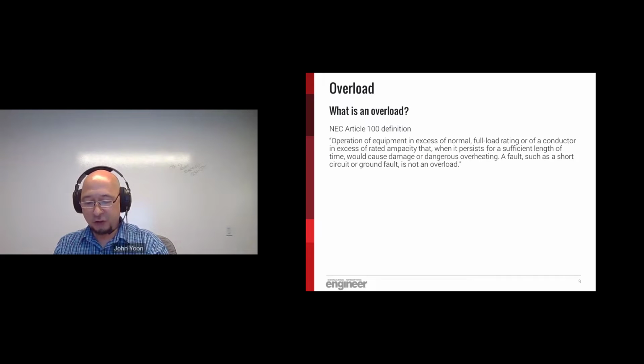But based on this definition, a fault such as a short circuit or a ground fault isn't an overload. If you read into this, the key takeaway should be that the current is flowing through the circuit that you designed, through that normally expected path, whether it be through a transformer, a motor, a feeder, whatever load or wiring method you may have connected to that circuit. However, the magnitude of that current is more than what you want. It could be sustained locked rotor current associated with a seized motor, or too many appliances plugged into a circuit. It could be any number of things.